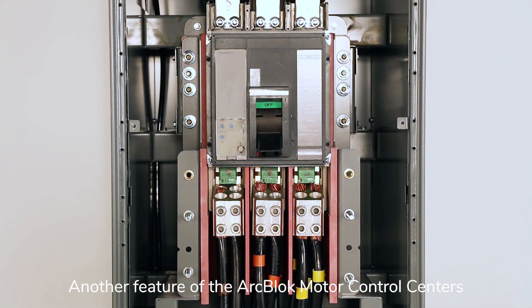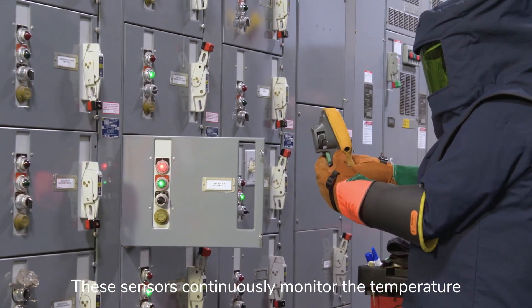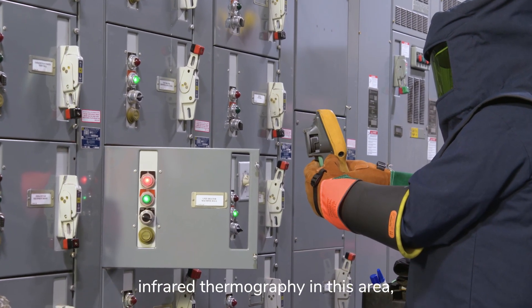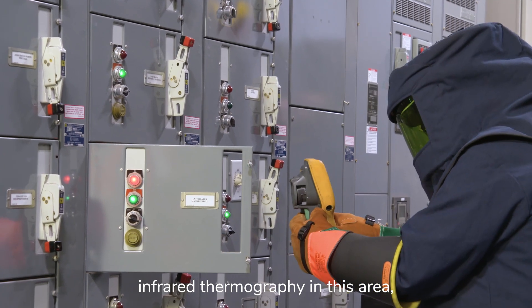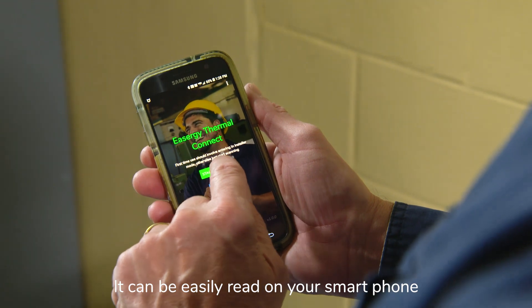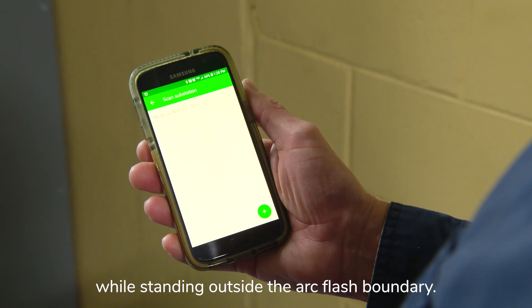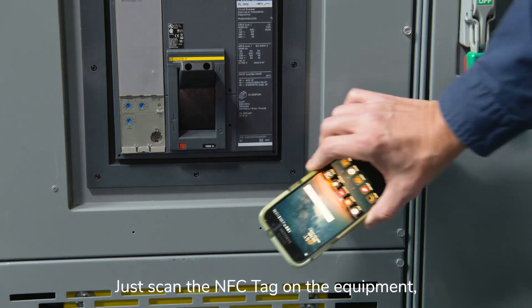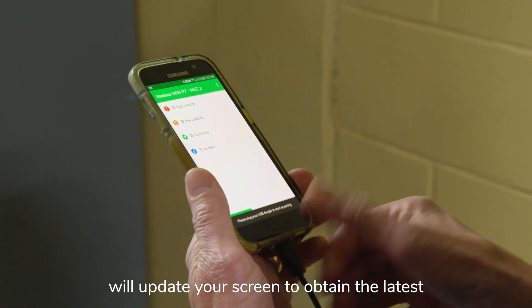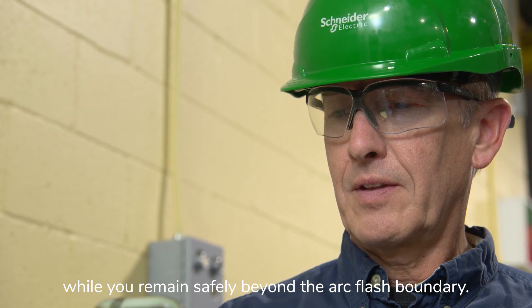Another feature of the ArcBlok motor control centers is wireless thermal sensors. These sensors continuously monitor the temperature of the line terminals, making it unnecessary to perform infrared thermography in this area, and thus avoid exposure to the line conductors. It can be easily read on your smartphone using our app and dongle while standing outside the arc flash boundary. Just scan the NFC tag on the equipment, open the app, and our wireless feed will update your screen to obtain the latest temperature data from your equipment, while you remain safely beyond the arc flash boundary.